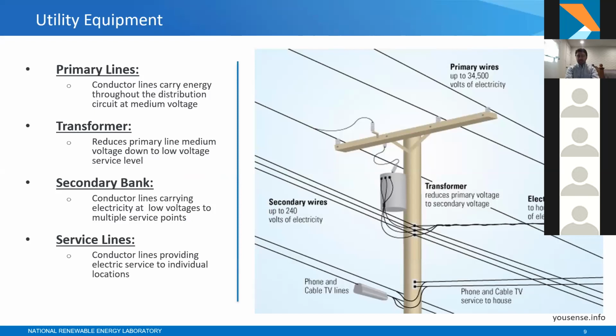But really the most important thing that utilities are going to be considerate of in terms of what equipment they need to look at is the distribution circuits. And along here, there's primary lines that carry the medium voltage power. And then there's a transformer that steps it down to a safe level for your facility. And then a secondary bank with smaller service lines that go from the transformer to your facility.